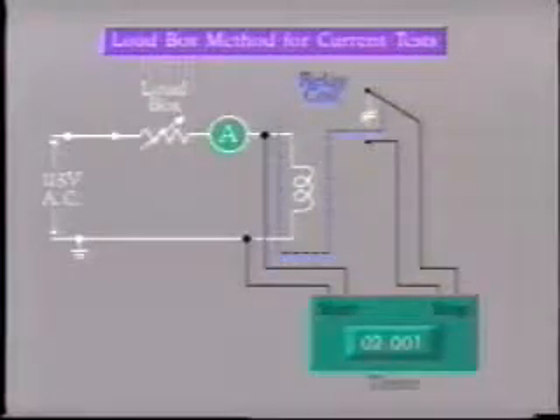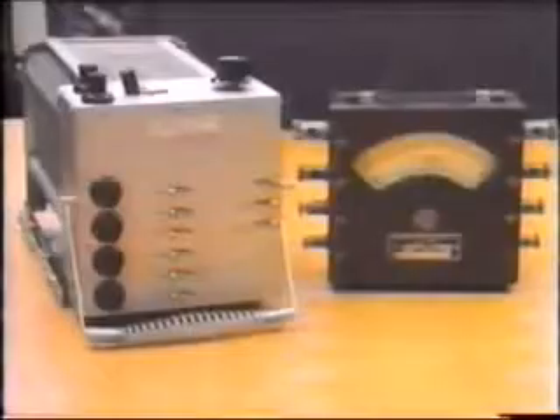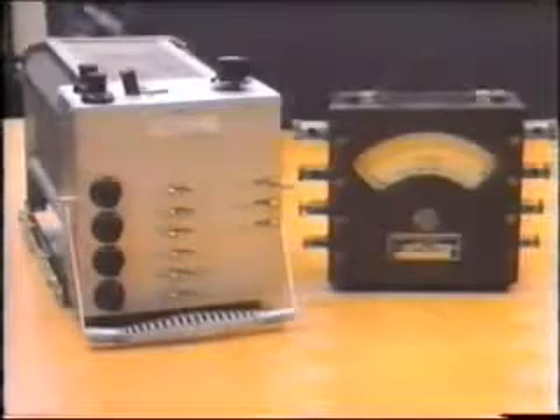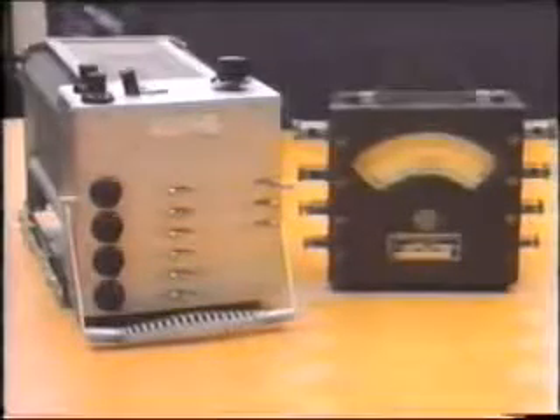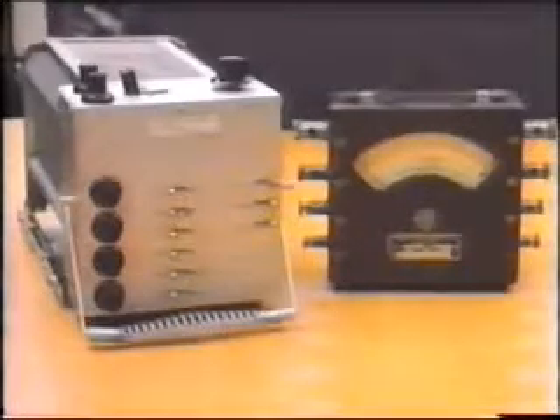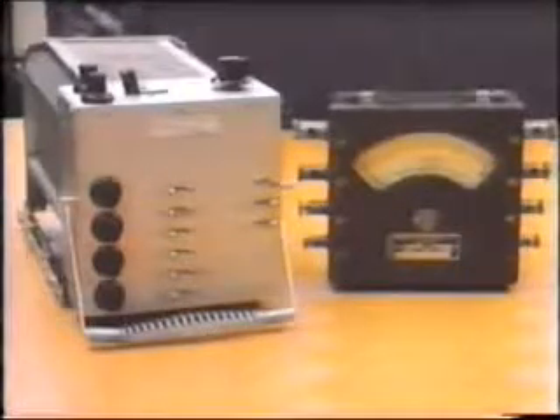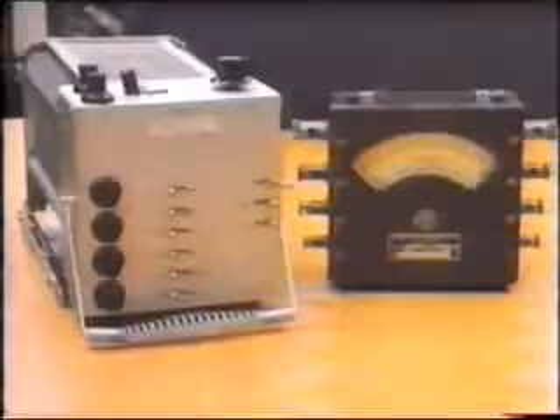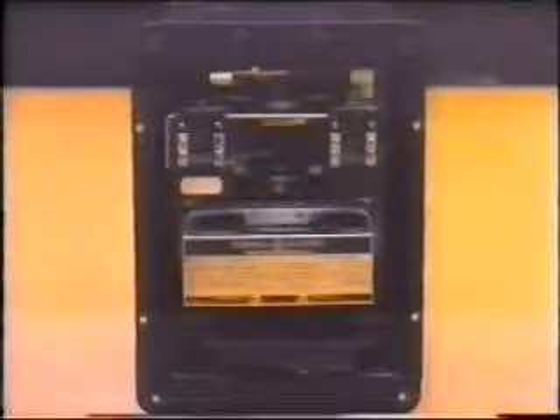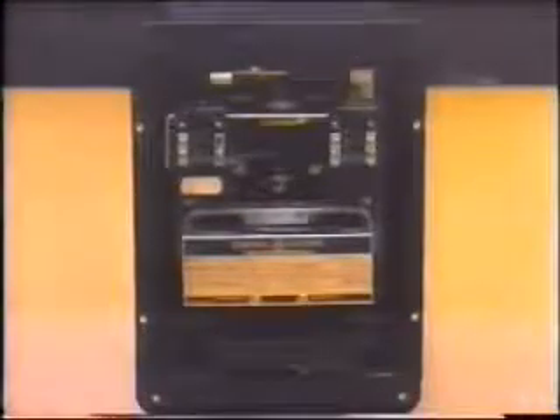We must be careful to begin with a very low value of current and set the ammeter on a high enough range for the expected test current. Also allow the resistance load box to cool off when necessary. This type of test set is usually limited in current output to about 30 amperes. But some relays, such as an instantaneous overcurrent relay, may require, say, 160 amps of test current.